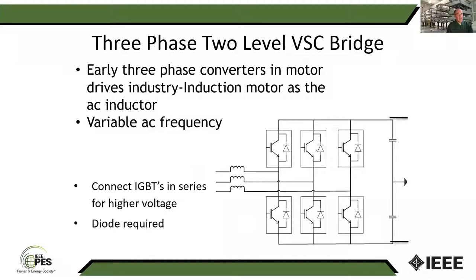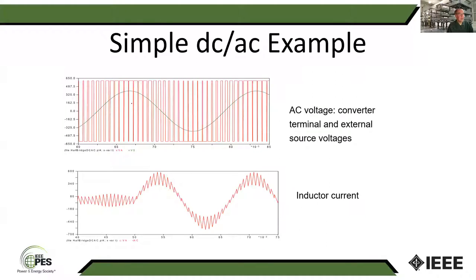And as we switch these, now we're basically producing line-to-line voltage differences between these points, as we say, if this one is connected to the positive rail and this one is connected to the negative rail, and we can produce that. To produce higher voltages, you may connect multiple power electronic devices in series. In this type of circuit, the IGBT does not have an inherent diode, so this gets added to it. So this topology goes back to the 1960s for motor drive applications. But this can produce a variable AC frequency because it's just synthesizing a voltage waveform.